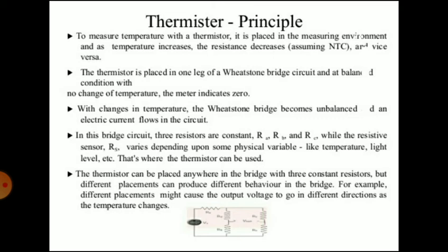The thermistor is placed in one leg of a Wheatstone bridge circuit, and at balance condition with no change of temperature, the meter indicates 0. Before that, we will see the construction. Thermistors are composed of a sintered mixture of metallic oxides such as manganese, nickel, cobalt, copper, iron and uranium.